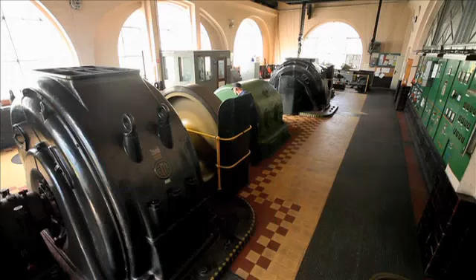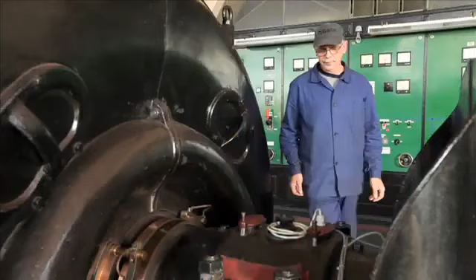The main turbines utilize the hydroenergetic potential of the water column, meaning the height difference between the level in the storage reservoir and the turbines. That is 196 meters. The output of the turbine is proportional to the head and the amount of water flowing through it. With turbines, there is an inverse relationship: the higher the water column above the turbine, the less water it needs per unit of output.